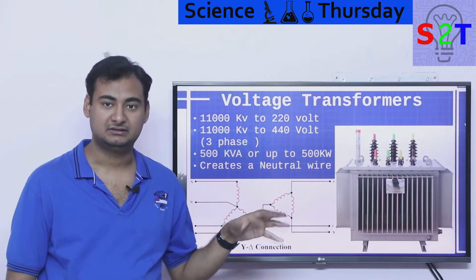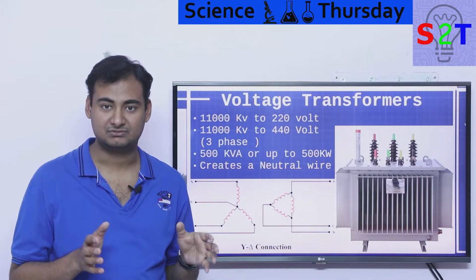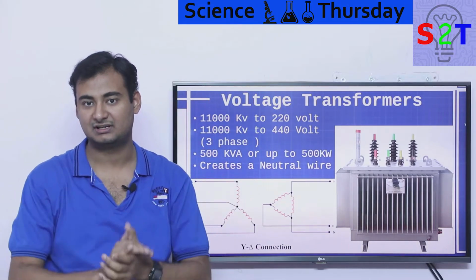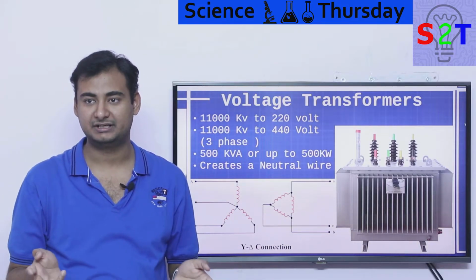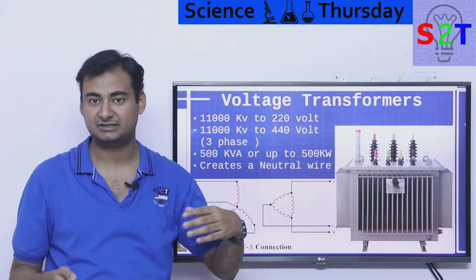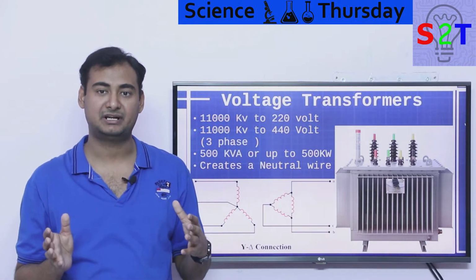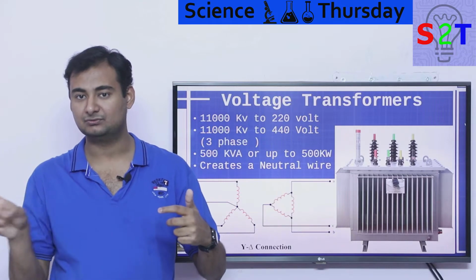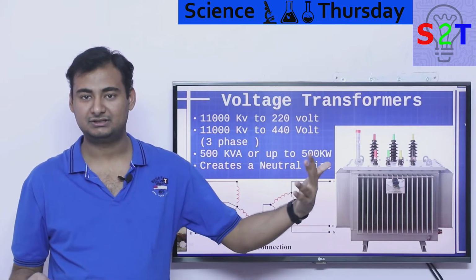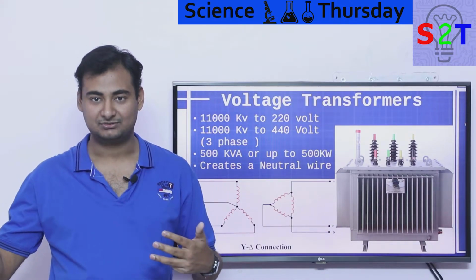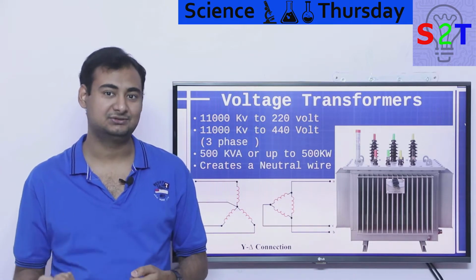Now you have to also understand, when you see these transformers, only 3 high voltage lines are coming in. How am I getting 4 lines out of it? In all the schematics you see about transformers, 2 wires come in, 2 wires go out. How do we have a scenario where 3 wires come in and 4 wires come out? You have 3 high voltage lines, so how are you getting a neutral?